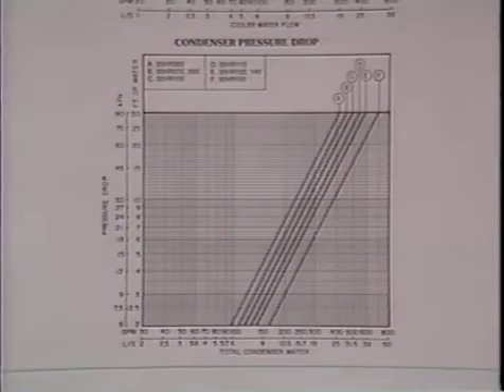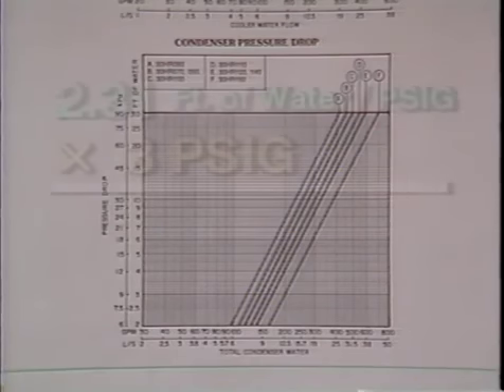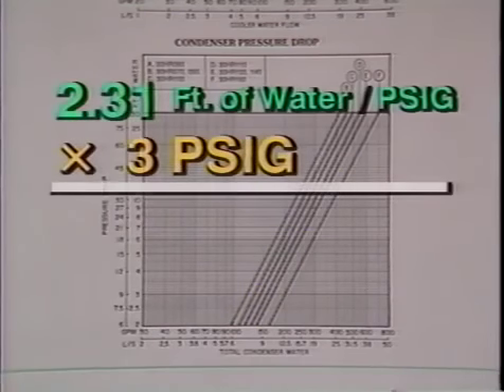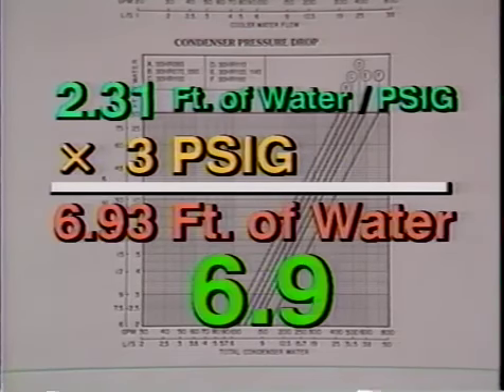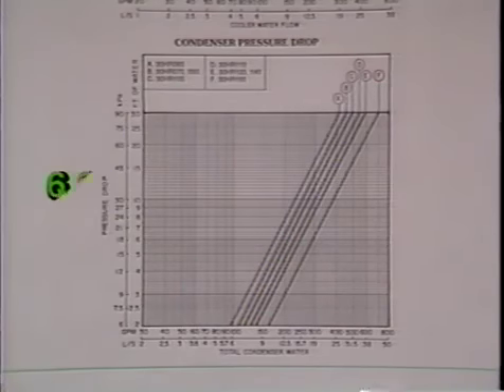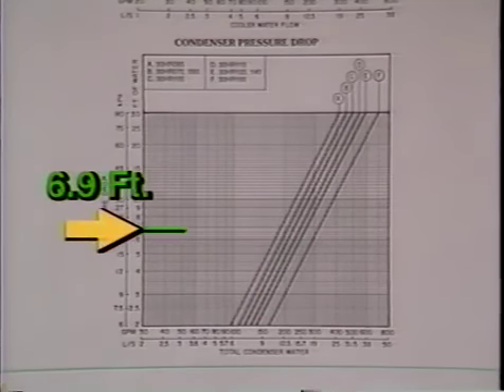This condenser pressure drop chart is in feet of water, so we must make a conversion. To do this, multiply the 3 psig pressure drop times the conversion factor, 2.31 feet of water per psig. Now, this equals 6.9 feet of water. If we start at 6.9 on the chart and read across to the 100-ton chiller curve and then down, we find a GPM of 225. This is the actual flow rate.